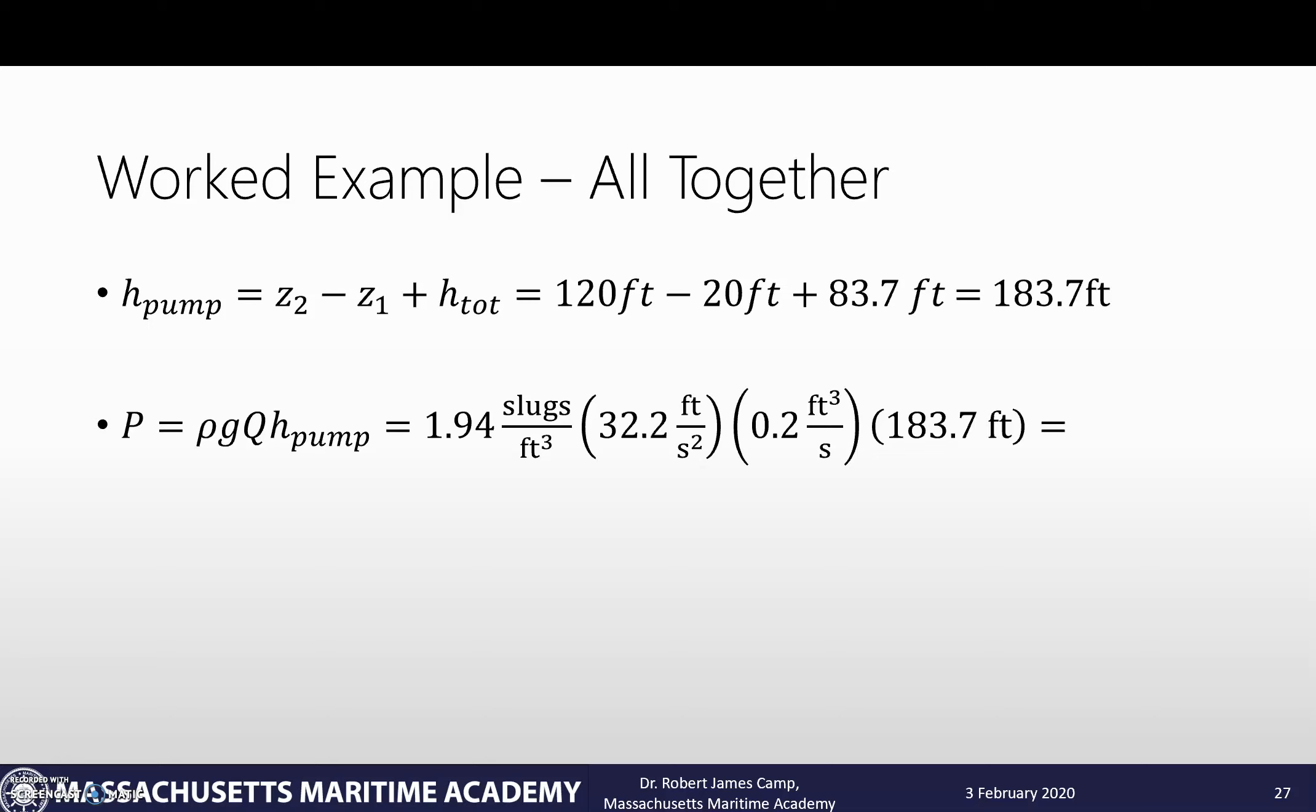ρ in our problem is 1.94 slugs per cubic foot, 32.2 feet per second squared, 0.2 cubic feet per second, times our 183.7 feet that the pump needs to supply to the system. That will come out to be 2300 foot-pounds per second. The problem asks for horsepower though, so we have to do a conversion. One horsepower is 550 foot-pounds per second, so once we make that last multiplication...